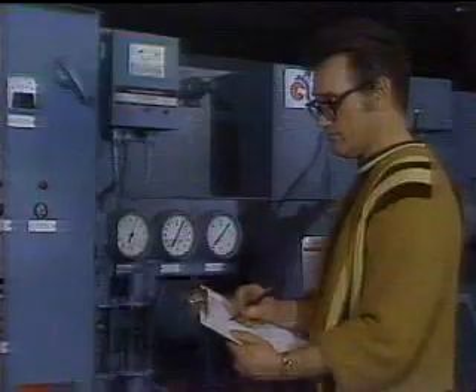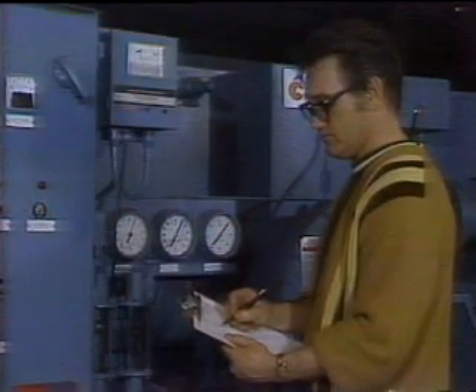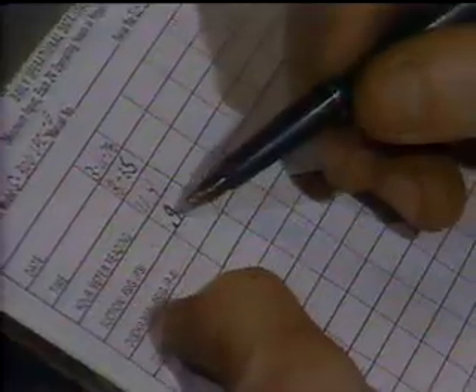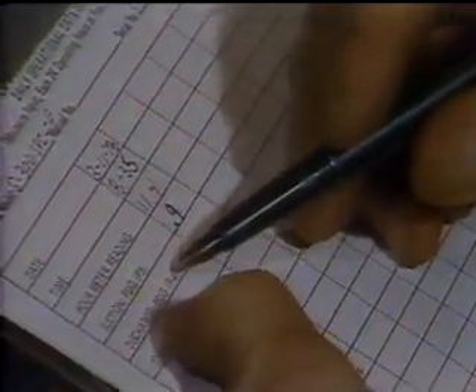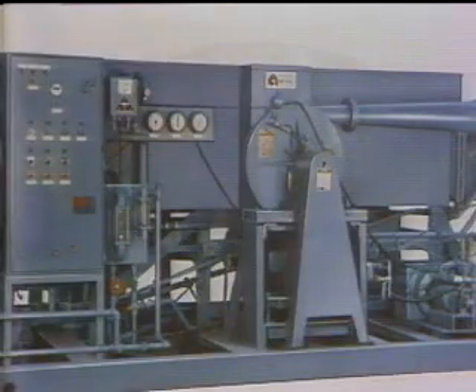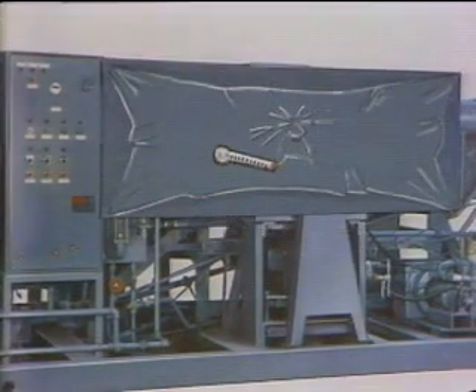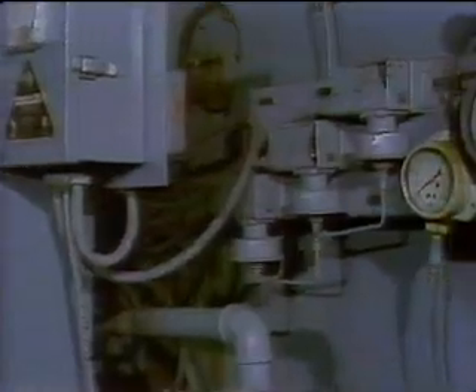This is the suction pressure. It monitors the steam pressure in the evaporator shell at the compressor inlet. It should read between 0.5 and 1.0 psig. Ours is reading 0.9. If the pressure is too high, the evaporator scale will form more rapidly, and if it's too low, the compressor will surge, causing compressor damage. The adjustment is made at the automatic heater pressure switch.